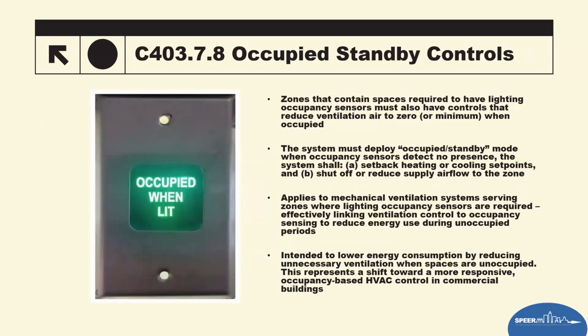And then occupied standby controls. This goes basically hand in hand with lighting control sensors. The idea is simple here. If the lights turn off because no one's in the room, the HVAC should also be adjusted as well. So under this section, any zone that requires lighting occupancy sensors must also have HVAC controls that switch into an occupied standby or unoccupied standby when the room becomes empty.